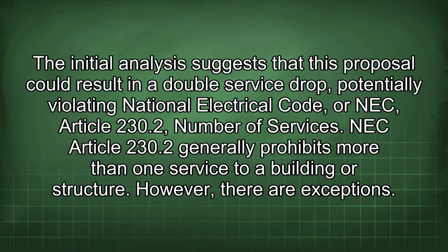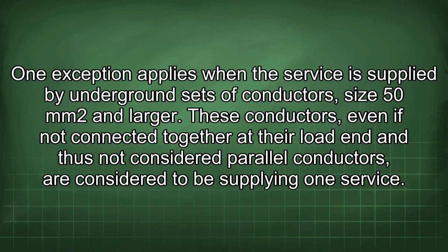The initial analysis suggests that this proposal could result in a double service drop, potentially violating National Electrical Code, or NEC, Article 230.2 number of services. NEC Article 230.2 generally prohibits more than one service to a building or structure. However, there are exceptions. One exception applies when the service is supplied by underground sets of conductors, size 50 mm2 and larger. These conductors, even if not connected together at their load end and thus not considered parallel conductors, are considered to be supplying one service.